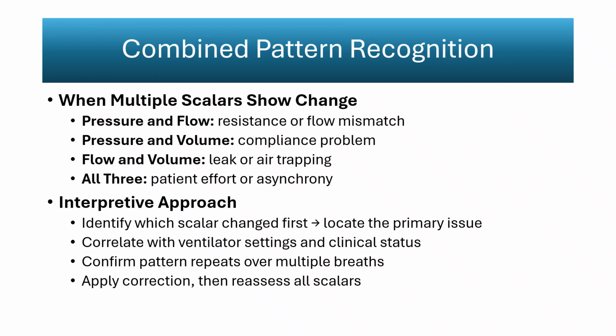When inspiratory volume exceeds expiratory volume, a leak is present. The ventilator successfully delivers volume, but part of that volume escapes through the airway instead of returning through the flow sensor. This is common with uncuffed endotracheal tubes, poor tube positioning, or loose circuit connections. The result is a visible gap between the inspiratory and expiratory limbs. Correction focuses on repositioning or securing the tube and tightening circuit fittings.